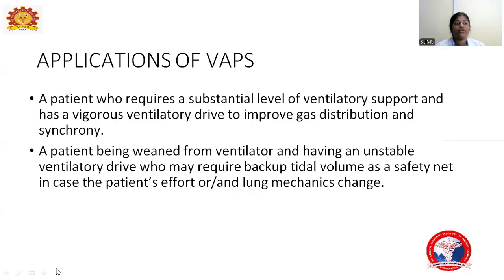So, where can you use this volume assured pressure support? A patient who requires a substantial level of ventilator support and has a vigorous ventilatory drive, to improve gas distribution and synchrony. A patient being weaned from the ventilator, having an unstable ventilatory drive, who may require backup tidal volume as a safety net in case the patient's effort or the lung mechanics change.